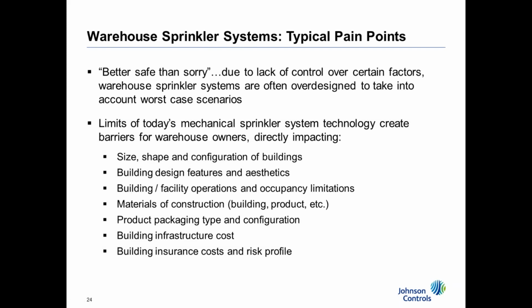Okay, so let's talk about some of the pain points. Now, as we just saw, sprinkler systems are designed with a safety factor in mind. So in the event of a fire, there's a phenomenon that occurs called sprinkler skipping. What that really means is sprinkler heads that you want going off may not necessarily operate, just because of the way the fire plume behaves. And there's really no way to control which heads go off.